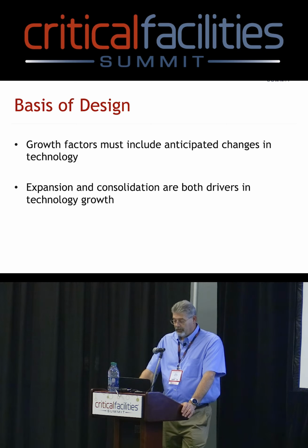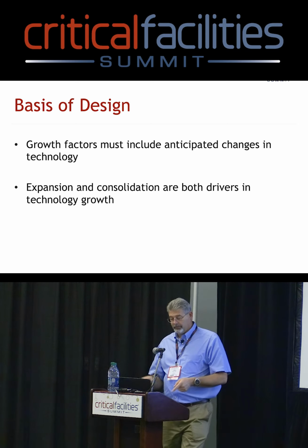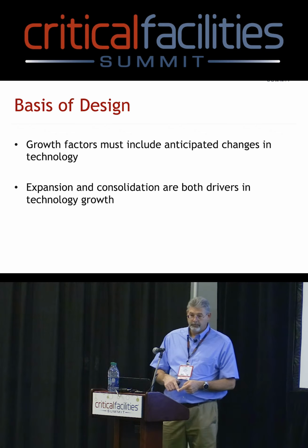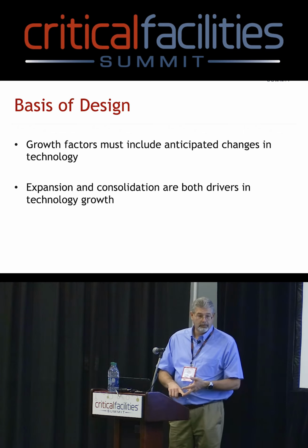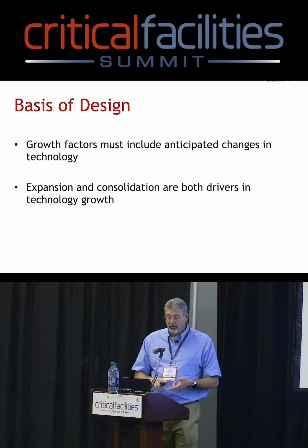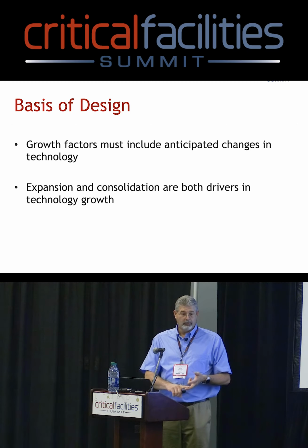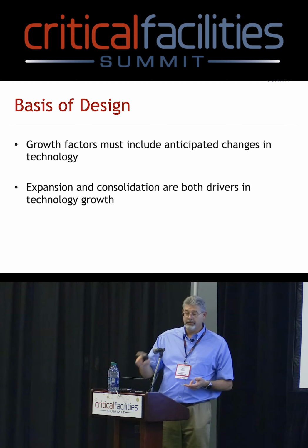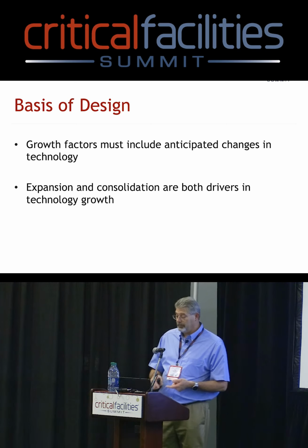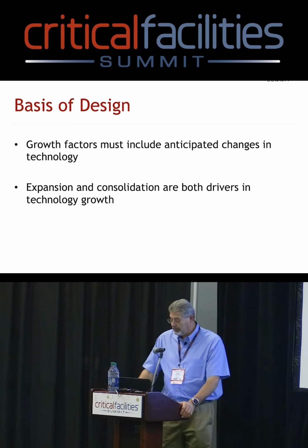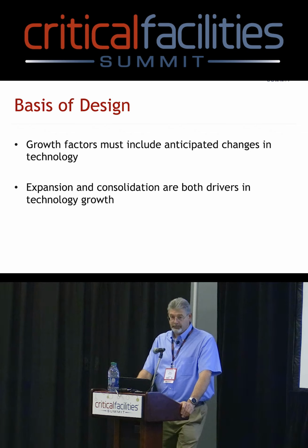When you're looking at your growth factors, that needs to be projected and calculated by technology type. Don't consider a 10% overall data center growth, 10% power and 10% cooling. It's more how many server percentages am I going to grow in that arena? How many percentages am I going to grow in network in that arena? And your network types.